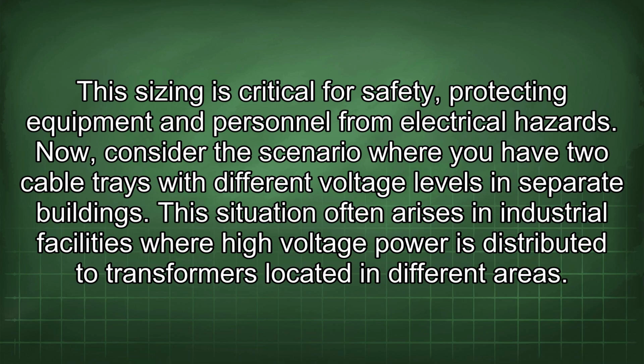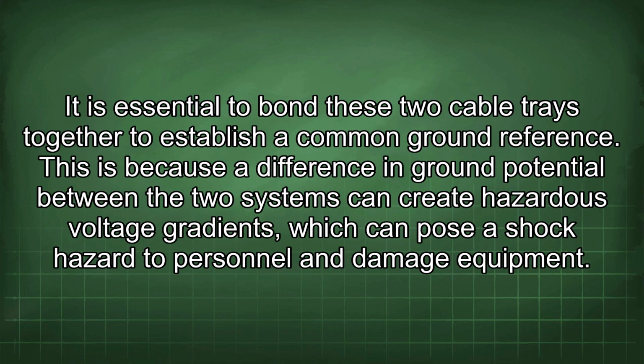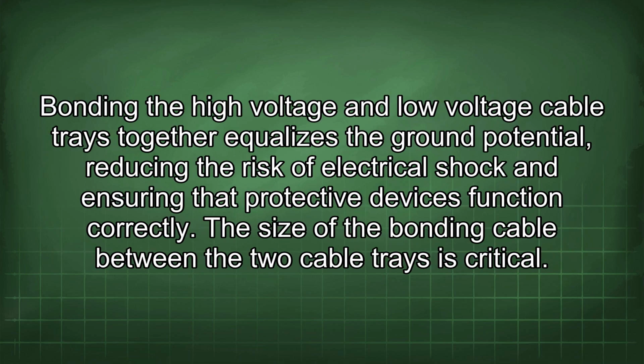Now, consider the scenario where you have two cable trays with different voltage levels in separate buildings. This situation often arises in industrial facilities where high voltage power is distributed to transformers located in different areas. It is essential to bond these two cable trays together to establish a common ground reference. This is because a difference in ground potential between the two systems can create hazardous voltage gradients, which can pose a shock hazard to personnel and damage equipment. Bonding the high voltage and low voltage cable trays together equalizes the ground potential, reducing the risk of electrical shock and ensuring that protective devices function correctly.